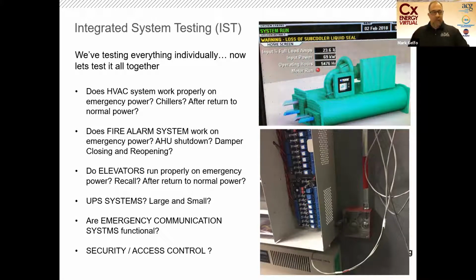So what we want to do is test the HVAC system, the chillers, on emergency power and make sure they still work after the transfer, and that the BAS system hasn't lost its mind after switching between normal and emergency and back again. Same with the fire alarm system - we're going to run the building on emergency power, test the fire alarm system, and make sure it can still shut down the air handlers and close the dampers and reopen them. Elevator recall is always a challenge for some reason, to make sure that when we switch to emergency power, the elevator recall works, and when we switch back. Same with other important systems: emergency communication systems, UPS systems, security and access control. It's very important to make sure those things work in all modes of operation.